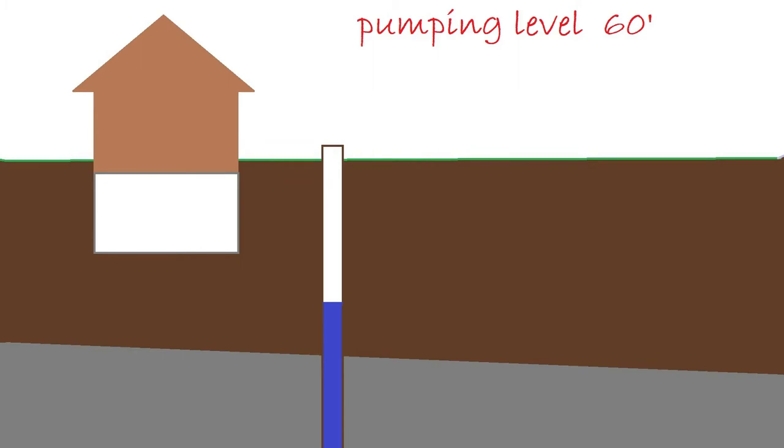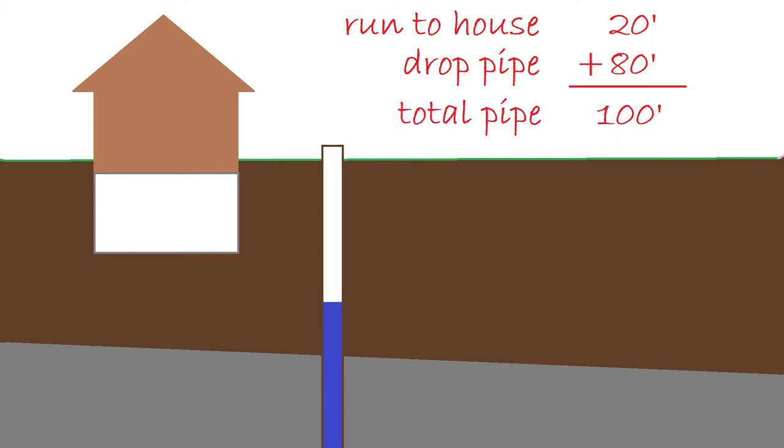Next we're going to figure out how much pipe we're going to need. Since we know the pumping level is 60 feet, all we have to do is set the pump deeper than that. 20 feet below the pumping level is usually a comfortable buffer. So let's set the pump on 80 feet of inch and a quarter schedule 80 PVC. From the well to the control room in the house we'll say is 20 feet. Adding up the run to the house and the drop pipe length we get 100 feet. Our friction loss is 9.06 feet of head per 100 feet of pipe. So since we have 100 feet of pipe, our friction loss is 9.06 feet of head.